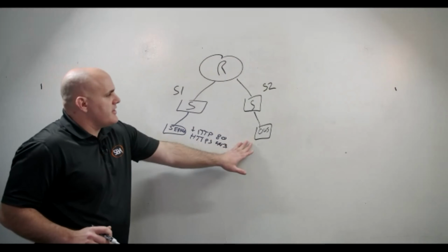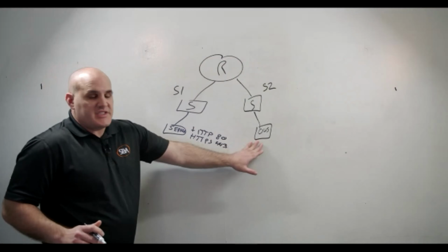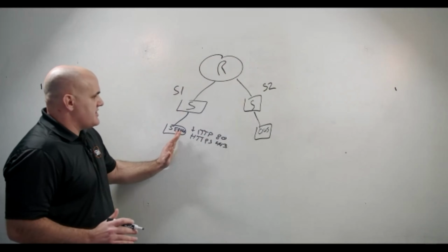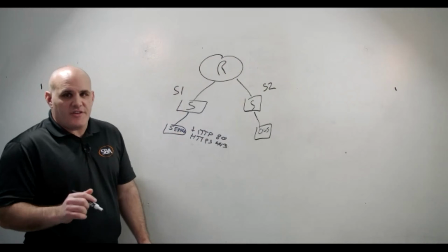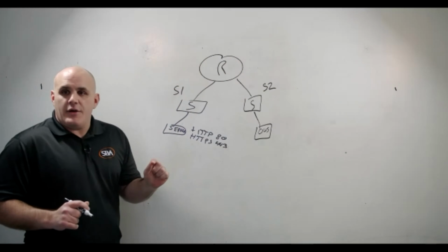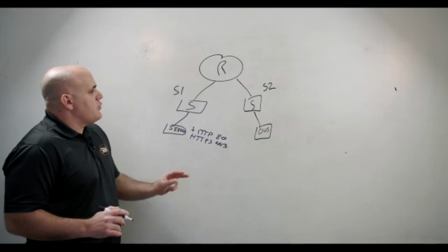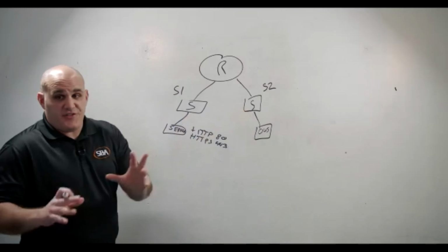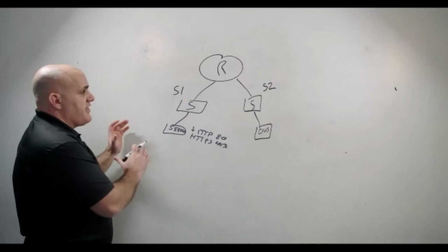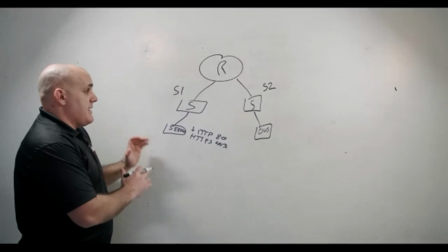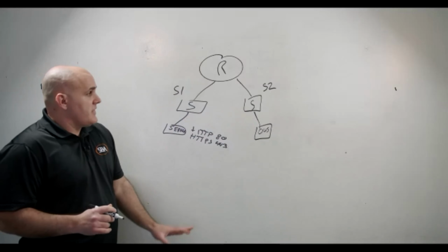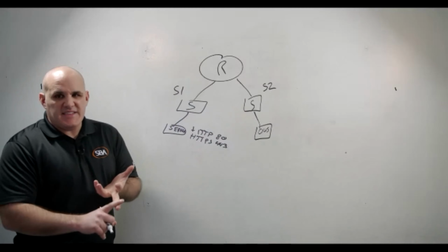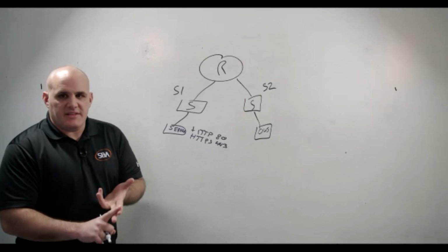So the first thing we say to ourselves is, from this operator workstation, can we ping the server? Can we ping that server? And if you can ping the server, then you know, without a doubt, it is not a routing issue. A route is a way that IP traffic is sent from one subnet, which is a different IP address scheme, to another subnet that is a different IP address scheme. So what I like to do is rule out subnet routing, and rule out ACLs and firewalls right off the bat. I like to knock those out.